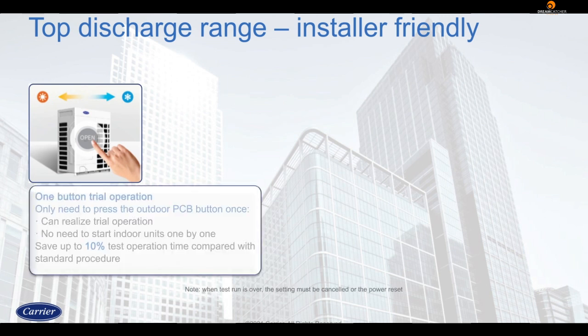The system comes with a one-touch trial operation where you can simply press the outdoor PCB button to realize the cooling or heating operation, which saves up to 10% on the test operation time, as you do not need to switch the indoor units one by one.